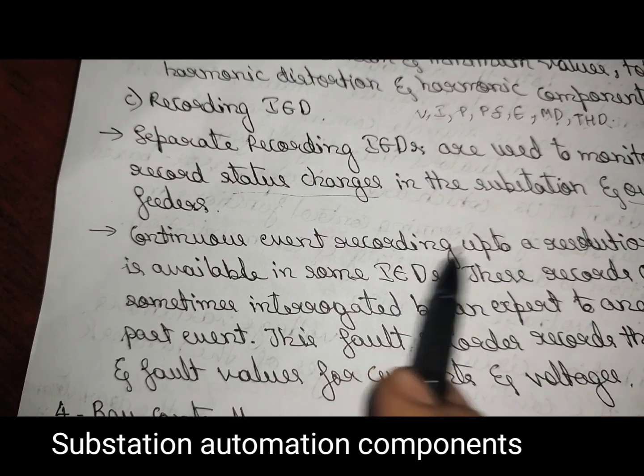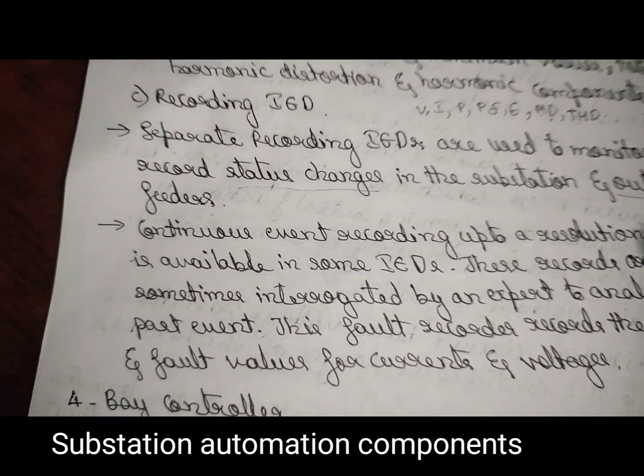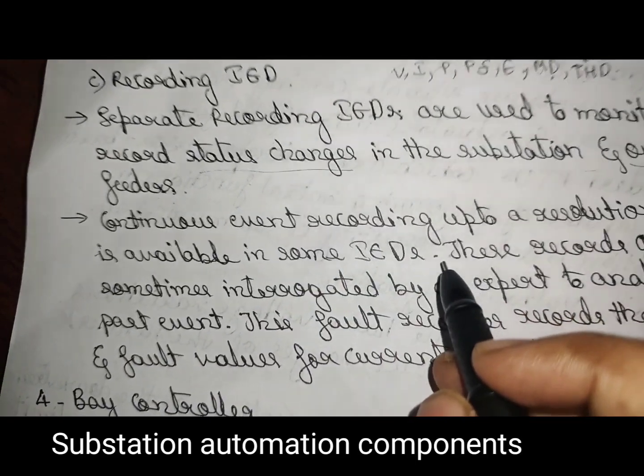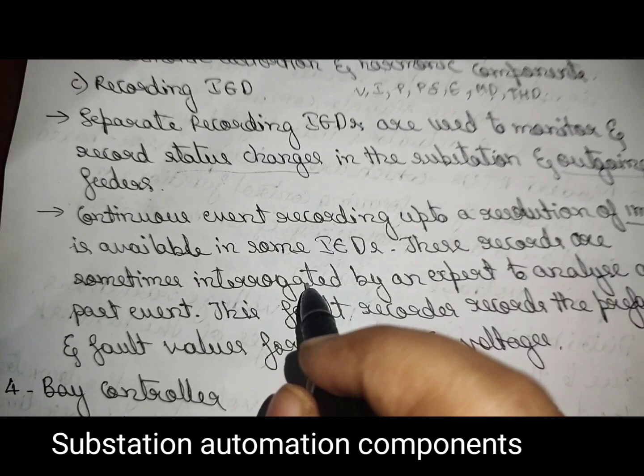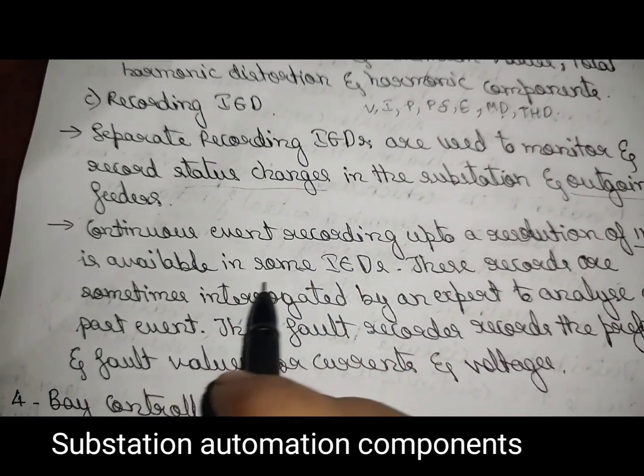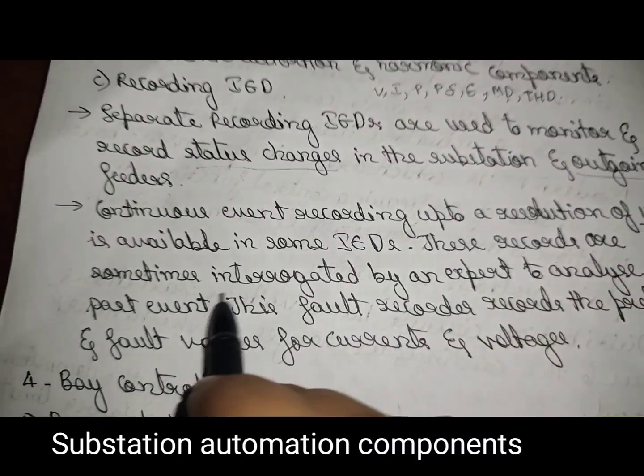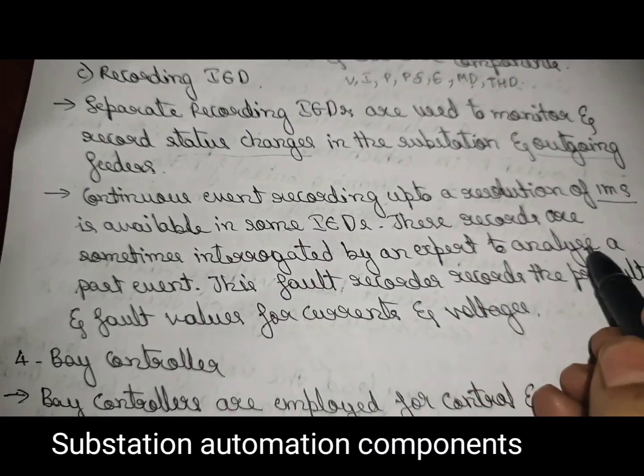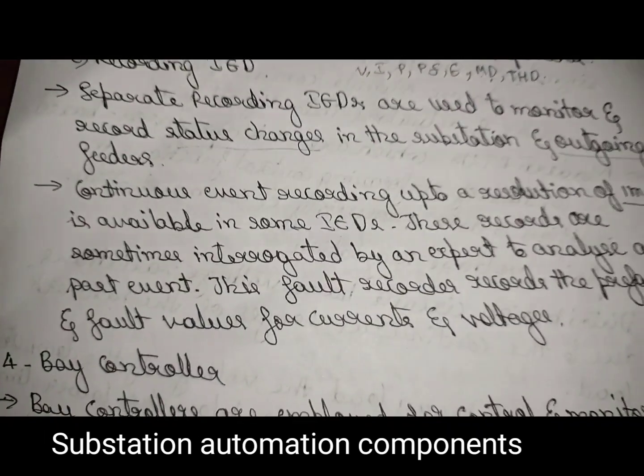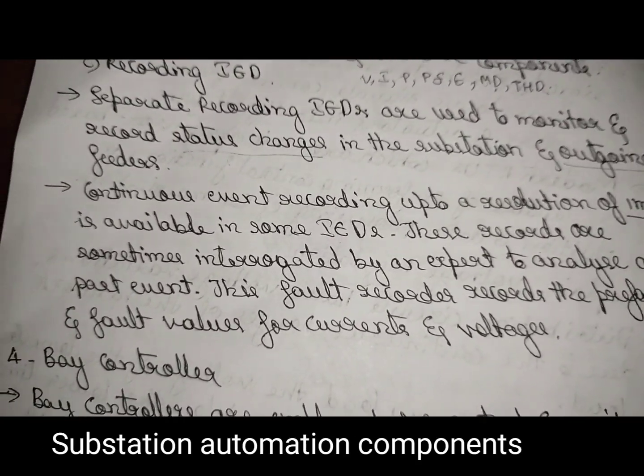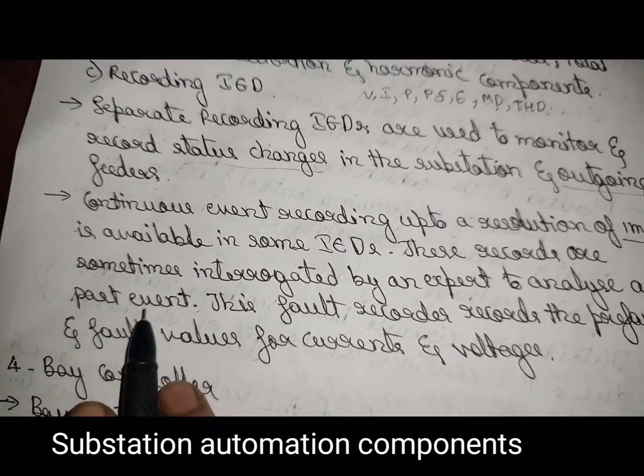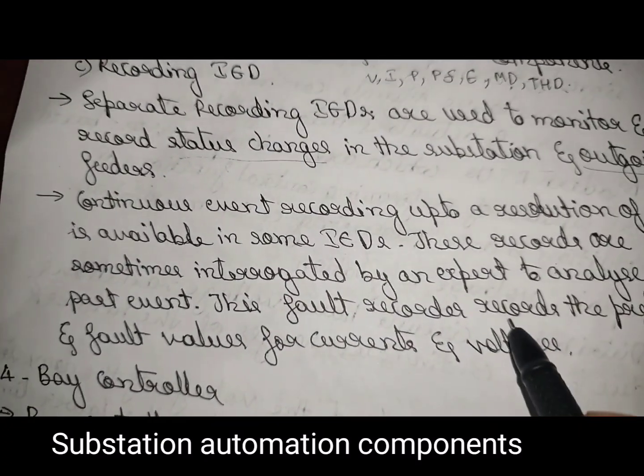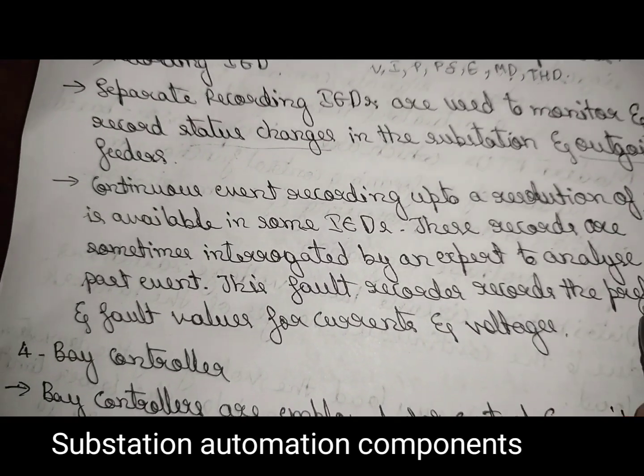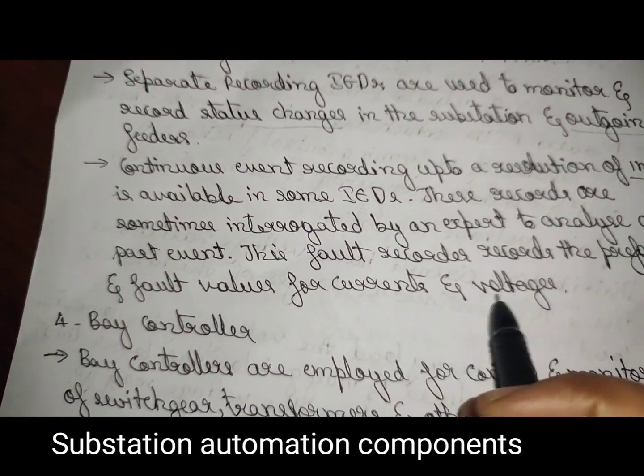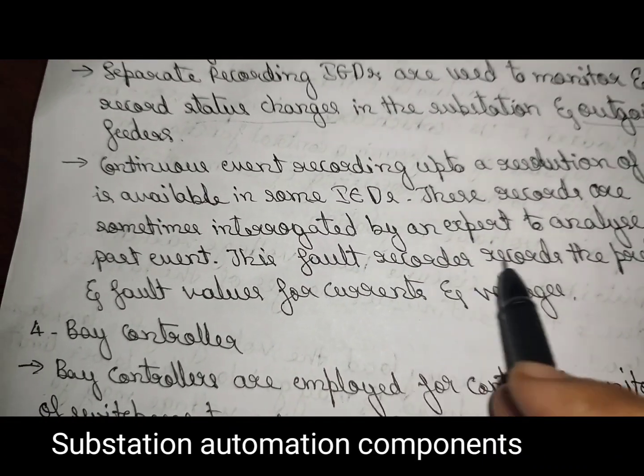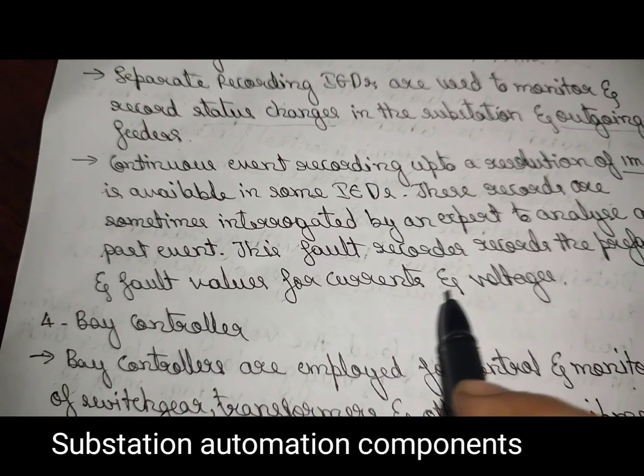Continuous event recording up to a resolution of 1 millisecond is available in some IEDs. These records are sometimes interrogated by an expert to analyze a past event. So they are not simply recording; the records will be interrogated by an expert to analyze a past event. This fault recorder records the pre-fault and fault values for current and voltage.